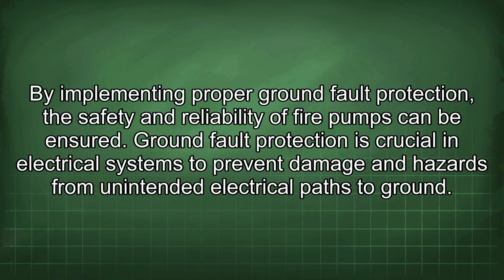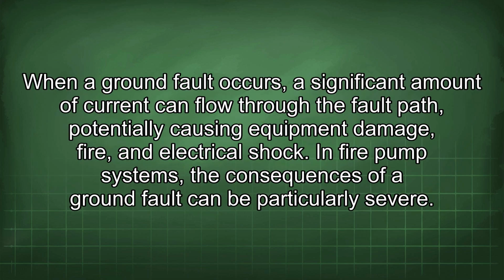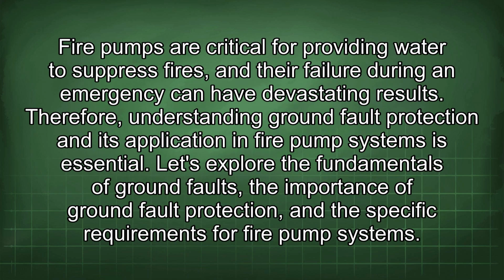Ground fault protection is crucial in electrical systems to prevent damage and hazards from unintended electrical paths to ground. When a ground fault occurs, a significant amount of current can flow through the fault path, potentially causing equipment damage, fire, and electrical shock. In fire pump systems, the consequences of a ground fault can be particularly severe. Fire pumps are critical for providing water to suppress fires, and their failure during an emergency can have devastating results. Therefore, understanding ground fault protection and its application in fire pump systems is essential.